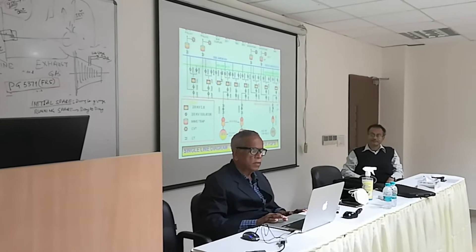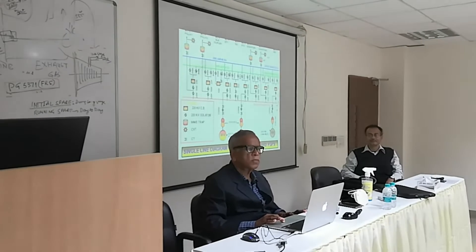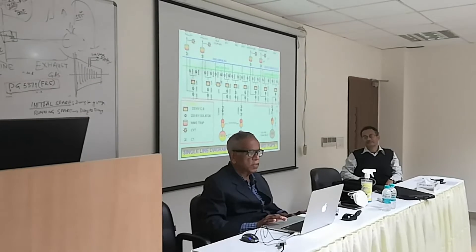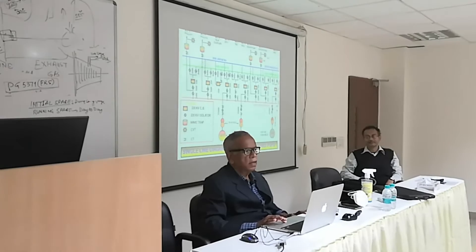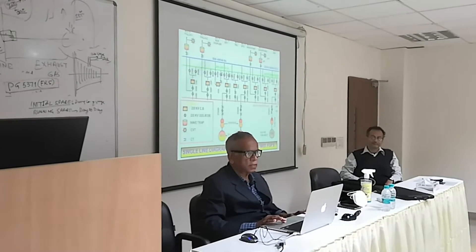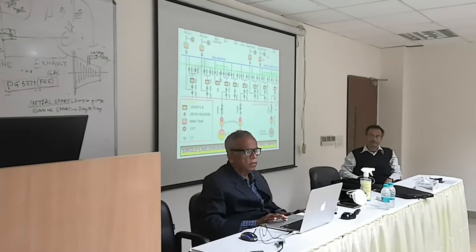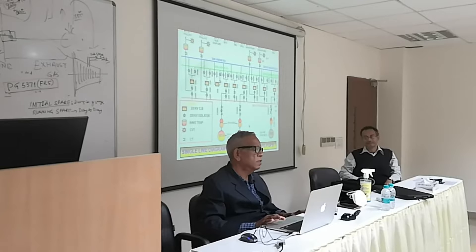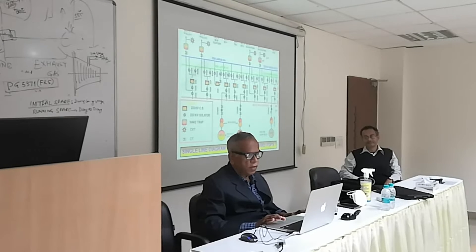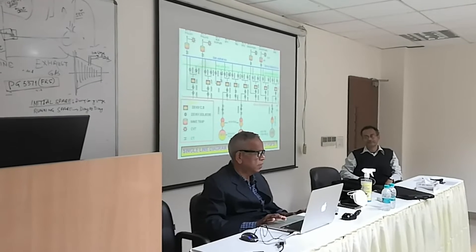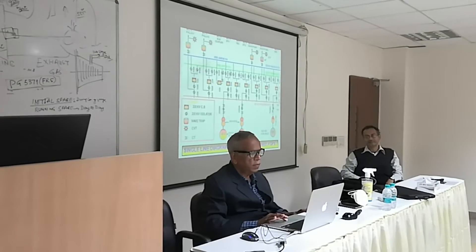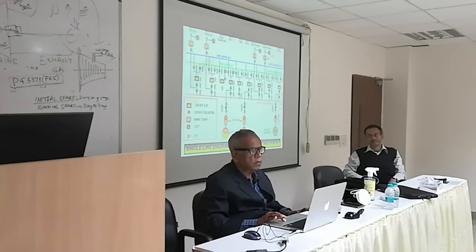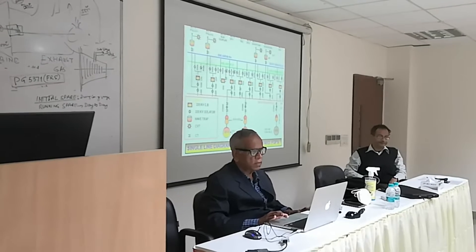Because this is a low voltage, if you transfer power at this low voltage, the value of the current will be very high, and due to the high currents there will be several losses in the transmission line. So we have the generating transformer, whose role is to raise the generator voltage to a higher voltage — say 220 KV or 400 KV. In this case we raise the voltage to 220 KV because it is a small power station of 437 MW.